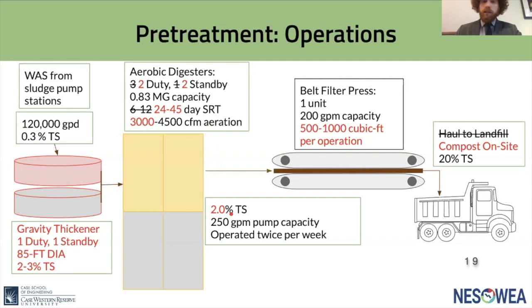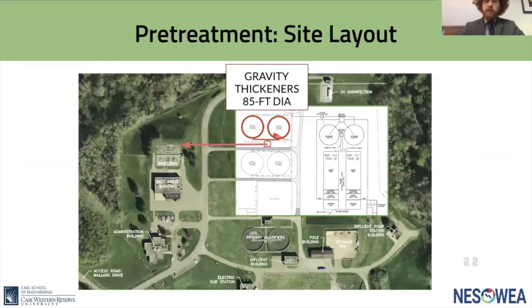These solids will come out at a consistent 2% total solids and will still be processed twice per week, producing 500 to 1,000 cubic feet per operation — all of which will now be composted on site at 20% total solids rather than landfilled. This renovation involves retrofitting the previous gravity thickeners, reinstalling their drives, renovating sludge pump station number one, and adding pumping from sludge pump station number three to the thickeners and then to the digesters.